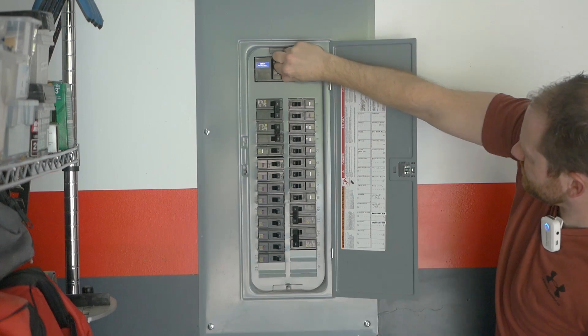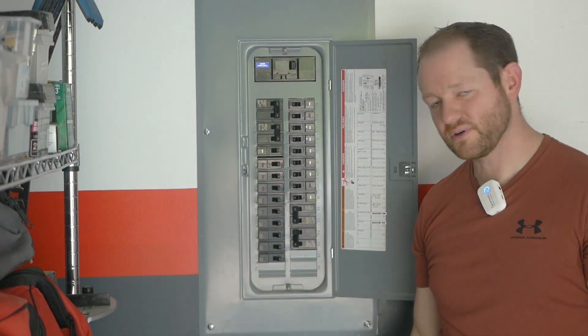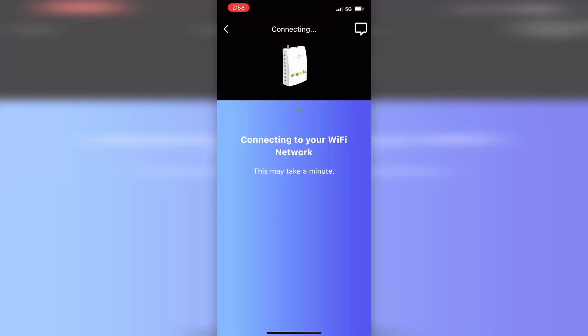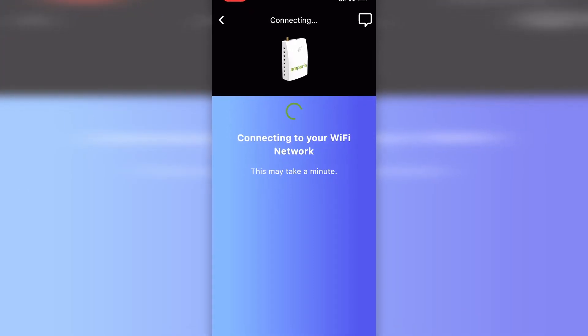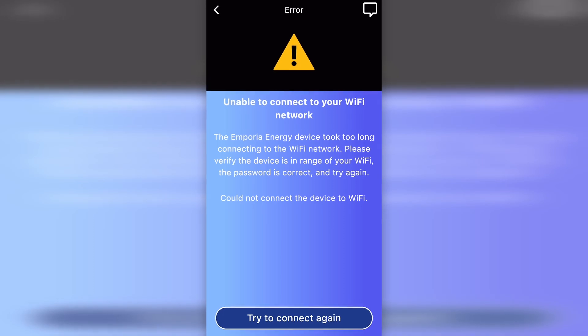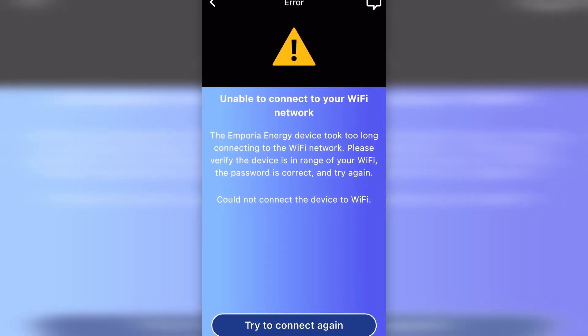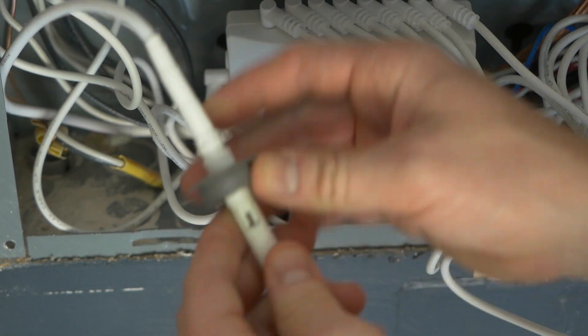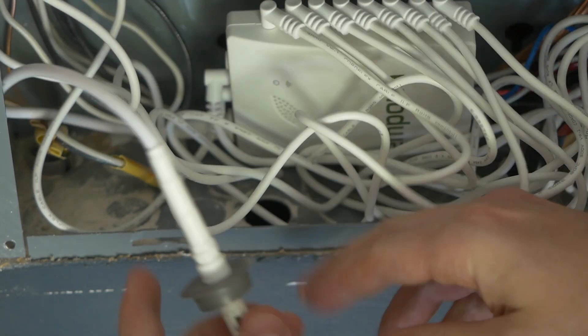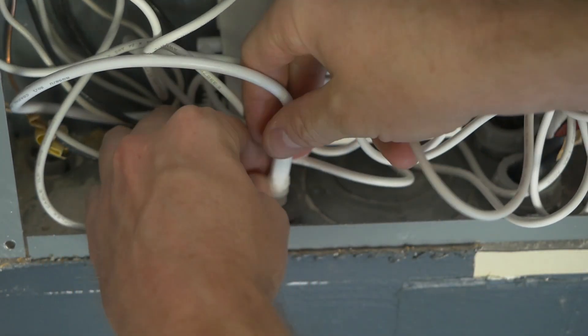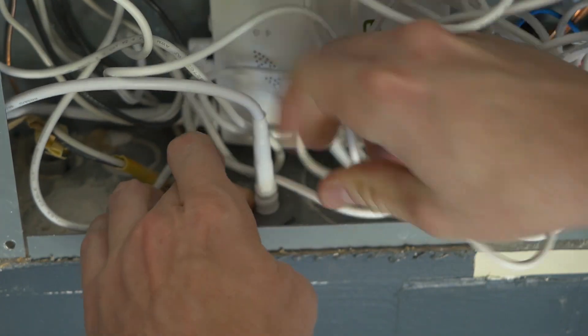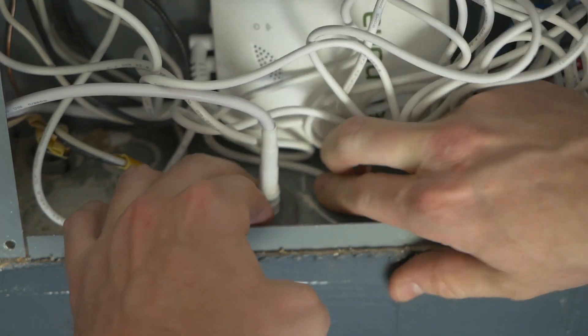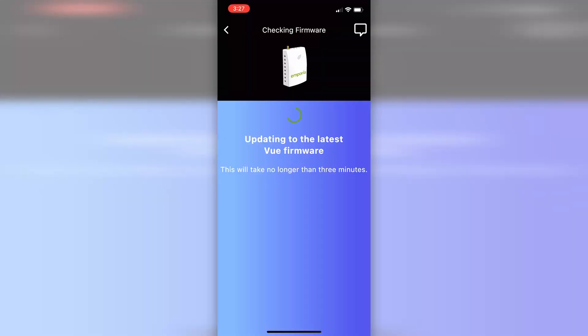During initial setup I ran into my first problem: I couldn't get the Vue to connect to my Wi-Fi. Thinking the panel itself was acting like a Faraday cage and interfering with the wireless signal, I opened it back up, removed one of the half inch knockouts, and stuck the antenna outside the box. This immediately solved the problem and I was able to connect up without further issue.